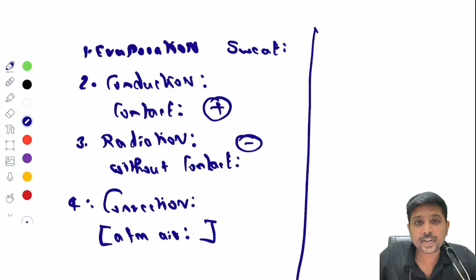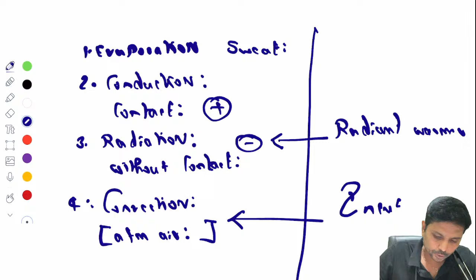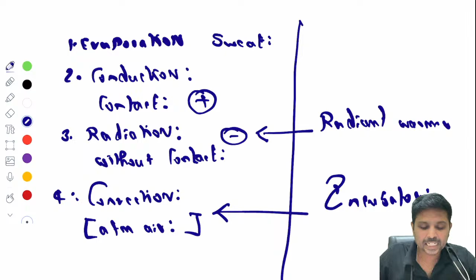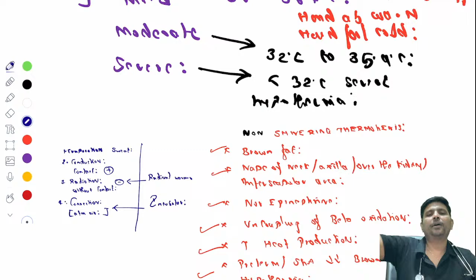Next point. So these are all the ways by which you lose your temperature. Then how does a radiant warmer work? Radiant warmers work based on the principle of radiation. In which mode does the incubator work to increase the temperature of the baby? Very good, incubator. The incubator operates through convection. So these are the four modes by which you lose or gain your heat. You can lose heat if the contact surface is cold, but when you have a warmer above you, you can get temperature from the warmer without any contact.